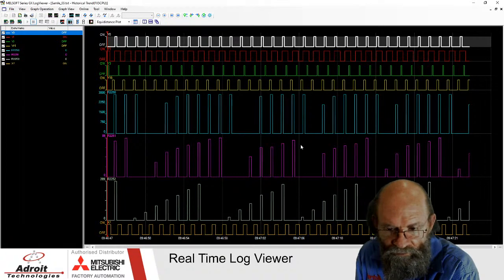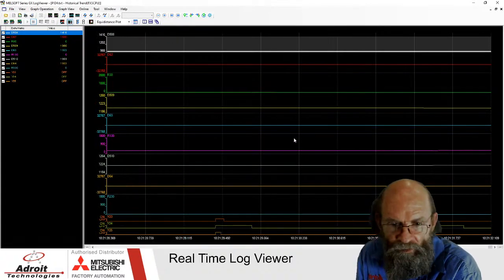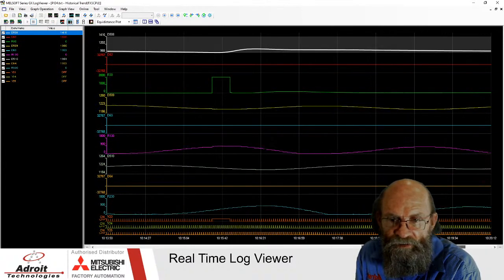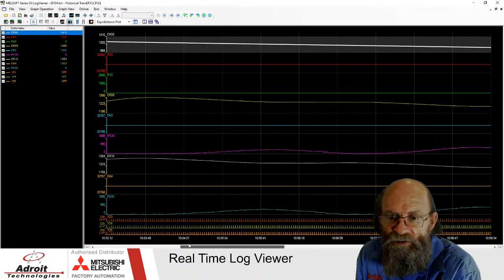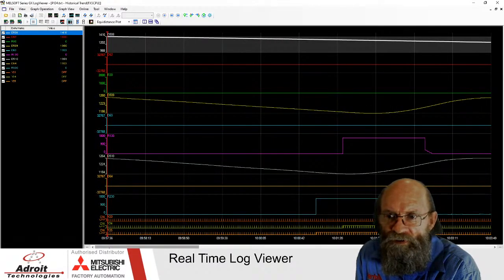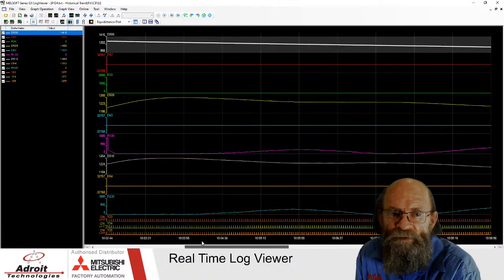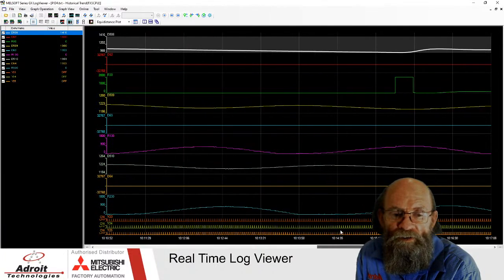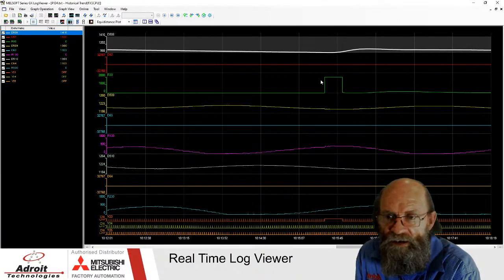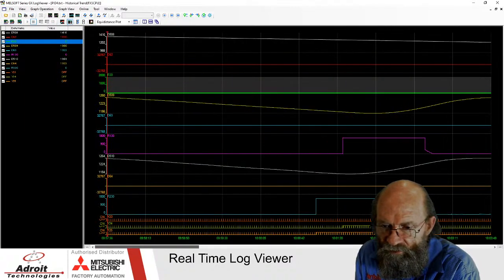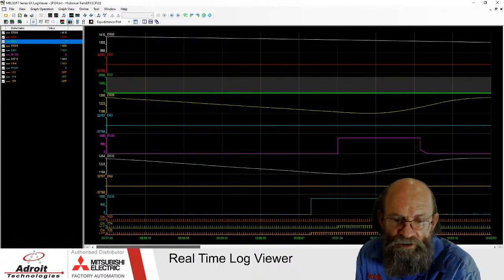It's quite a substantial amount of data that I've recorded there. Okay, there we go. So I can zoom out and get some very interesting information out. On this specific system, there are 5 PIDs running, and I've recorded the first 3 just to monitor some set points and what the temperature is doing based on the auto tune. If I'm not mistaken, the auto tune was started somewhere about here or earlier. No, the auto tune was started much earlier. I just recorded halfway during the auto tune.